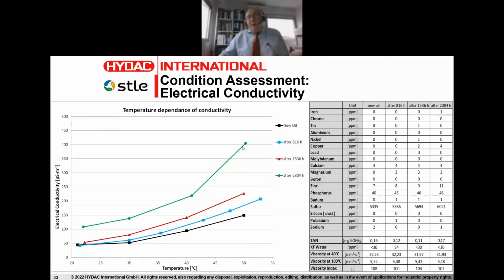And this is what happened. This is a new oil after 800 hours, 1500 hours, and 2300 hours. So within approximately 6 months, and this is a temperature dependence of the conductivity signal, and we can see that it did change quite dramatically. And what was another very encouraging sign for us is that nothing else has changed. So additive content here has remained the same. Even zinc content, plus or minus a few ppm, and this is a zinc-free oil, has remained relatively the same.